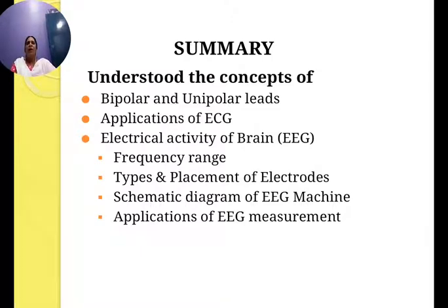Then the last one, we have the writing part. It is usually the ink type direct writing recorder. The best type of pen motors used in EEG machines have a frequency response of about 90 Hertz, and inkjet recording has a response of 1000 Hertz.